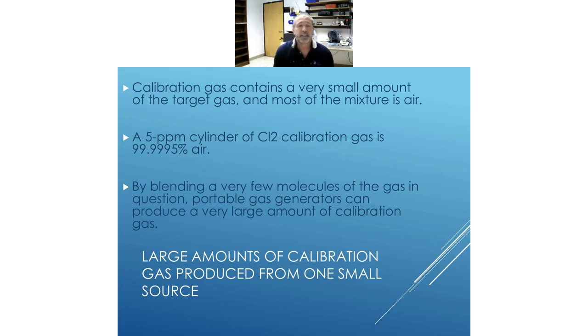So calibration gas contains a small amount, as we spoke, of the target gas, and the rest of the mixture is air. So a 5 part per million cylinder of chlorine calibration gas is 99.9995% air. So when you buy that cal gas cylinder, you're essentially buying air with just a little tiny bit of chlorine in it. So you can see where we can get large amounts of calibration gas from one small generating source. Some of the sources we have will put out as much gas as 100 58-liter cylinders of gas.